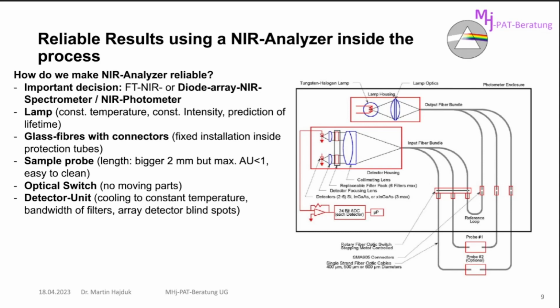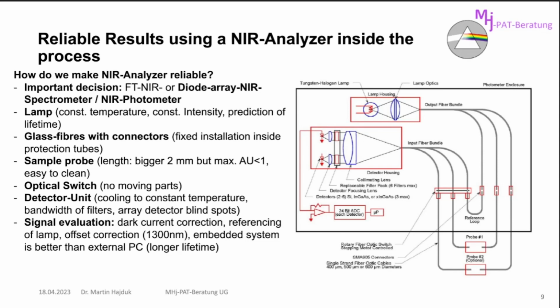Coming to the detector unit, the energy of the photons in the NIR area is very low, and so the detector noise depends on the temperature. So we have to cool the detector, but also in this kind of multichannel photometer, the filters. We have to cool the detector and also the filters. In other words, if we have a spectrometer in this position, we also have to cool the detector. So very important is cooling to a constant temperature, normally minus 30 degrees Celsius. We have to take care about the bandwidth of the filters. If we are using array detectors, sometimes we have blind spots. So this is very important if we make a transformation of our calibration.